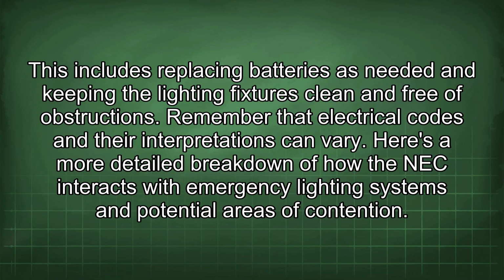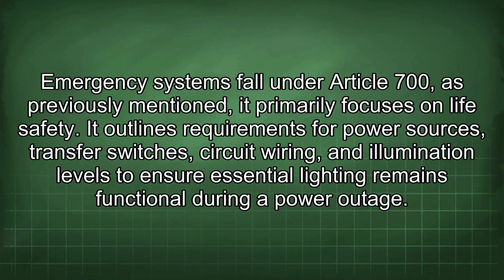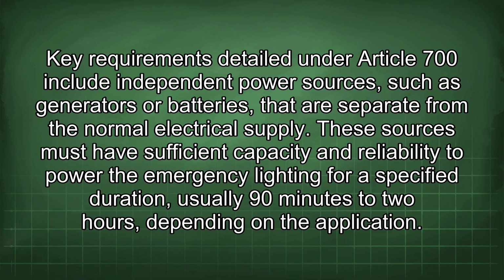Remember that electrical codes and their interpretations can vary. Here's a more detailed breakdown of how the NEC interacts with emergency lighting systems and potential areas of contention. Emergency systems fall under Article 700. As previously mentioned, it primarily focuses on life safety. It outlines requirements for power sources, transfer switches, circuit wiring, and illumination levels to ensure essential lighting remains functional during a power outage. Key requirements detailed under Article 700 include independent power sources, such as generators or batteries, that are separate from the normal electrical supply. These sources must have sufficient capacity and reliability to power the emergency lighting for a specified duration, usually 90 minutes to 2 hours depending on the application.